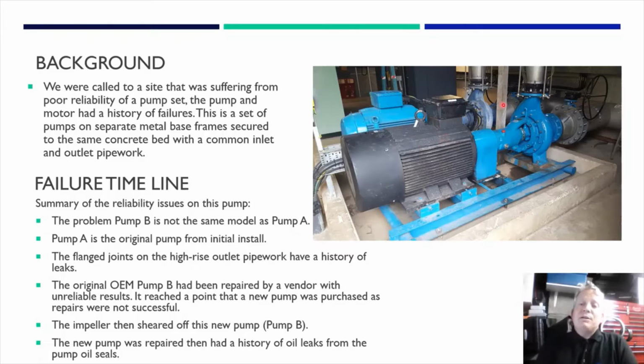So straight away we can look at there and see an effect of a failure. Some vibration was causing this pipe to move and crack. They've been having pump issues, motor issues. Logically you'd go, well, it's on this metal frame here on some sort of project which they probably forgot to concrete in the base to make it stiffer.